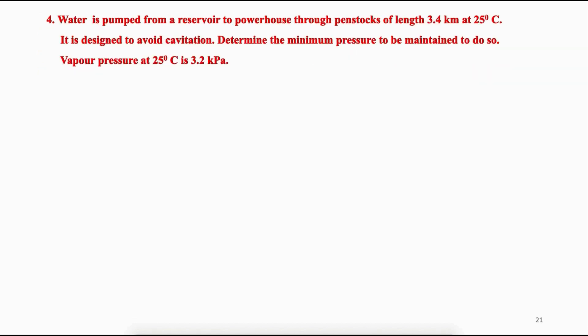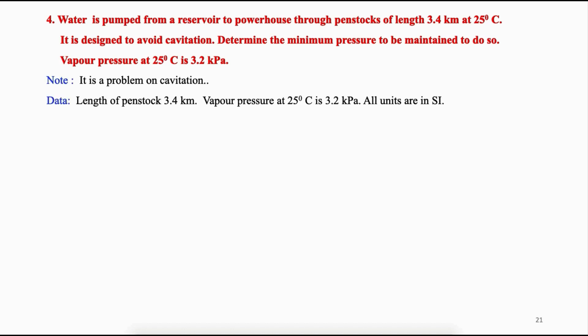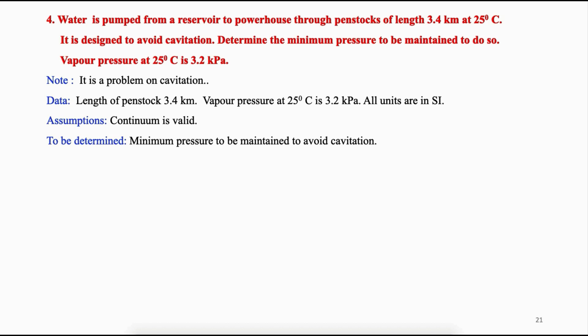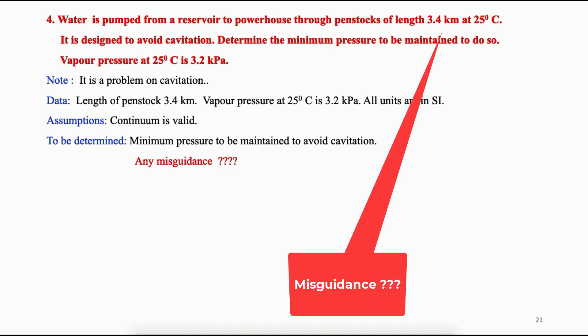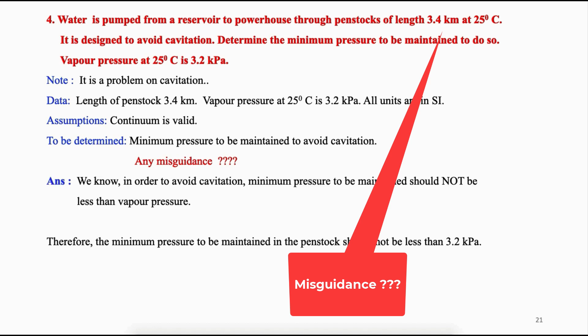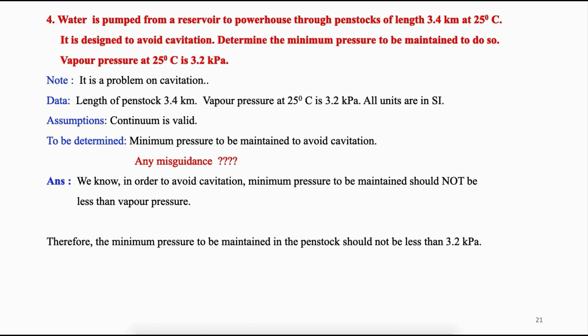Problem 4: Water is pumped from a reservoir to a powerhouse through penstocks of length 3.4 km at 25°C, designed to avoid cavitation. Determine the minimum pressure to be maintained. Vapour pressure at 25°C is 3.2 kPa. Note that the length of the penstock is redundant data — to avoid cavitation, only pressure matters. Therefore, the minimum pressure to be maintained in the penstock should not be less than 3.2 kPa.